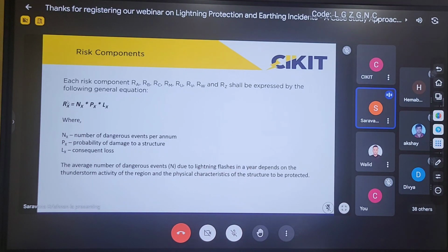So if I am performing this risk assessment calculation, the modifications that I will make for reducing the risk due to lightning will be mainly on this probability of damage to the structure. That is the area where we have control. And the last one, LX, is the consequent loss. What will be the losses incurred to the particular structure or site due to lightning?